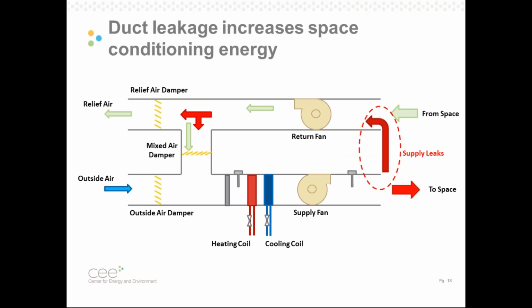So I've got this cartoon here of a mixed air handler unit. We borrow our supply fan from before. This time it has supply ducts, and those supply ducts are traversing a ceiling plenum. So above a drop ceiling, the supply ducts run out to the diffusers. And that ceiling plenum actually serves as the return pathway for the return air. In this situation, our supply air is leaking directly into our return duct, the ceiling plenum. If we follow that supply leak from our supply duct through our leakage path right into our return, it finds its way directly back into the return side of the system.